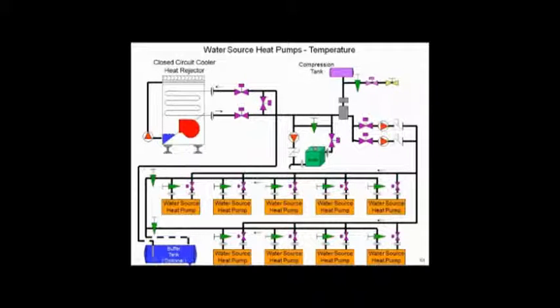So you're saying to me, Chris, if I get down to 60 or lower, I'm going to turn the boiler on and add some BTUs. Absolutely. So what is your return temperature at 60 to the boiler? It's going to be cold. And that boiler is going to rain unless you do something to fix it. So what we did here was we put a bypass around it with a circuit setter and blended it to try to make sure that the return water temperature never got down below 130, because these non-condensing boilers, if you rained in them, you tore them up. It became a huge maintenance issue.